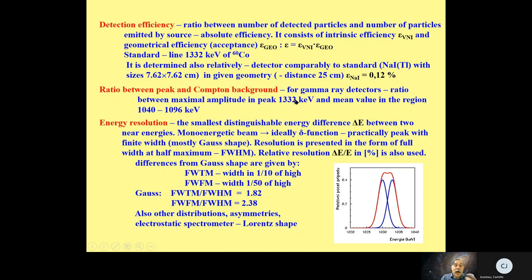For energy measurements and determination of line energies, it is important to know the energy resolution of the detector. This is the smallest distinguishable energy difference between two nearby energies. If you have a monoenergetic beam, ideally it would be a delta function, but practically in any detector you obtain a finite width — mostly a Gaussian shape. Resolution is presented in the form of full width at half maximum (FWHM).